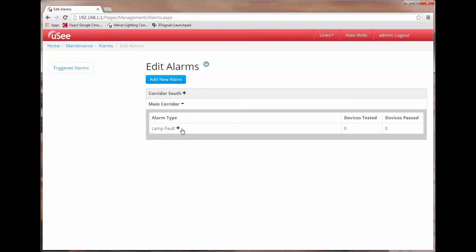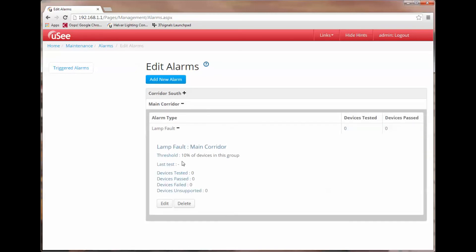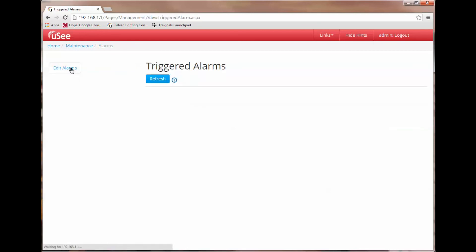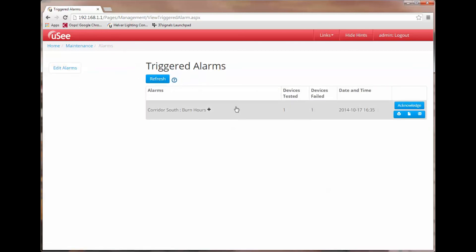So now main corridor is an alarm type of lamp fault and we can see that the threshold is 10% of the devices in this group would have to fail before the alarm would be triggered and the action taken. Let's just go back to our triggered alarms and you can see obviously we've still got our burn hours alarm triggered but in fact there is no trigger for our lamp failure alarm.